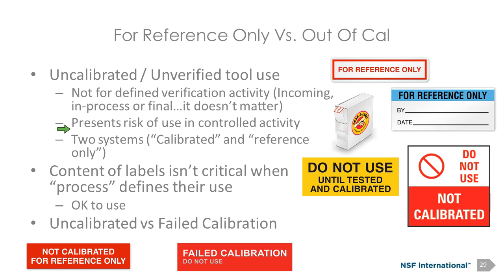Okay? Ultimately, again, the standard is looking to have confidence in our measuring results by controlling the quality of the tools, demonstrating that they're fit for use. So having the process in place to ensure that you're only using those tools for measurement, for inspections, for test is important. Now, I'm certainly not saying we can't have tools that are there for setups, or for an engineer who wants to tinker at his bench. That's perfectly fine. But we need to understand, and we need to have a system associated with what these can and can't be used for, and how we control those so that they don't get mixed into that calibrated population.